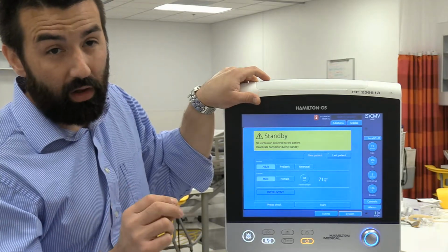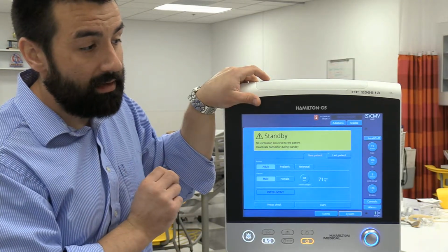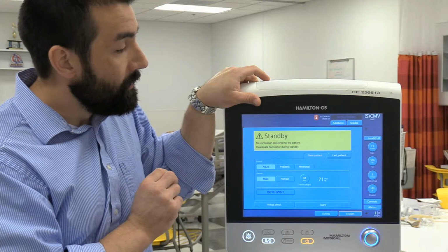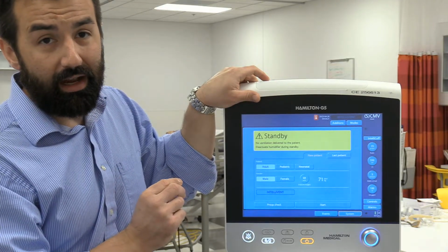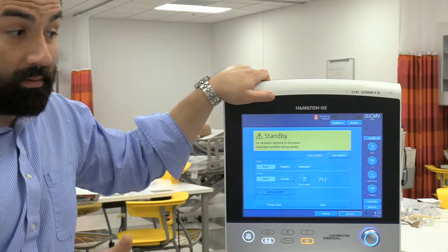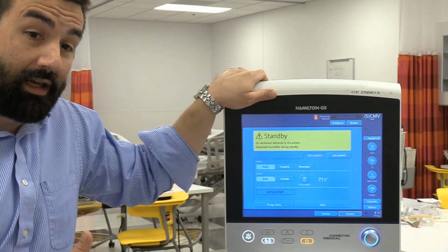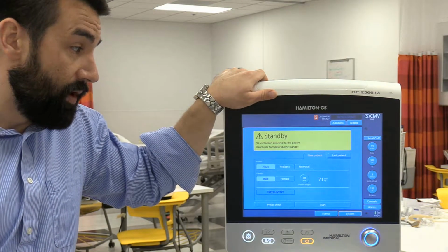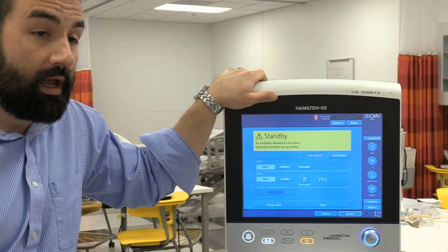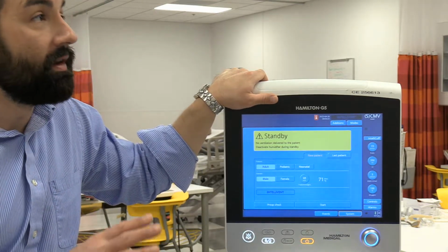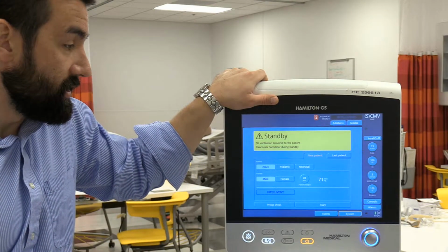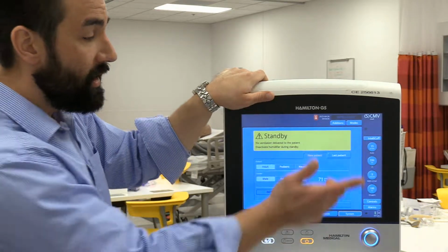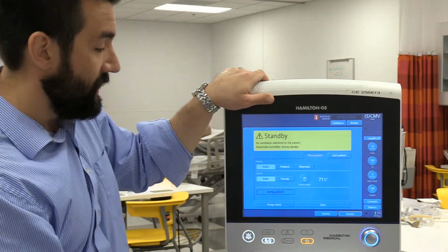adjustments. I will say out of all the vents, it is important that if you know their height, you put that in as soon as you can, because there's a mode on this called ASV that actually comes up with the tidal volume and ventilating parameters based upon this patient's height and their ideal body weight, okay? So if you have this incorrectly and somebody switches over, it's not possibly going to give appropriate ventilator settings for that patient. So it's always important to get in. You can't access this after initiating ventilation. I kind of show you that here.